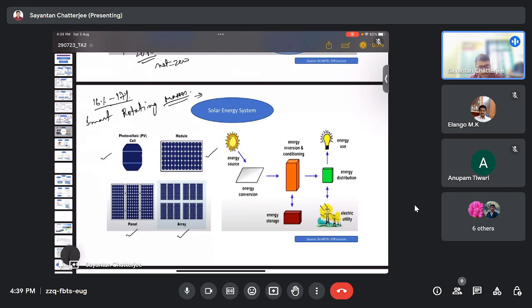These rotating masses aided a lot - suppose there's a sudden decrement in load, this is coped up by the synchronous generator's rotational inertia, so it won't allow the frequency to suddenly fall. If load decreases, frequency increases, so the inertia won't allow the speed to fall down suddenly, thereby maintaining the frequency constant. But renewable resources, especially solar, don't have this kind of inertia.